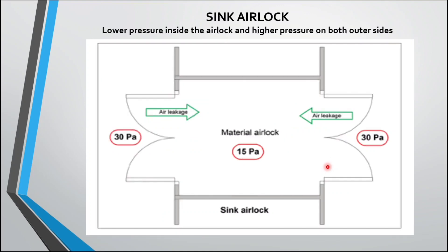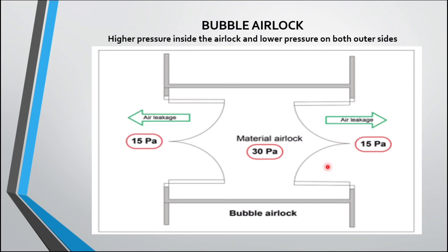In a sink airlock, there is lower pressure inside the airlock and higher pressure on both outside areas. The airlock becomes a sink, meaning air flows from both sides into the airlock. In a bubble airlock, there is higher pressure inside the airlock and lower pressure on both outer sides, so air flows from the airlock outward to outside areas.